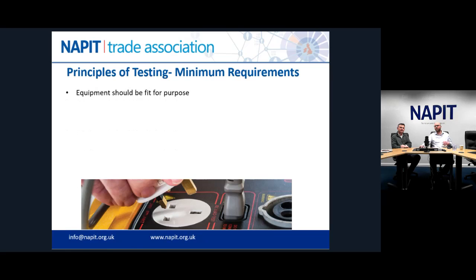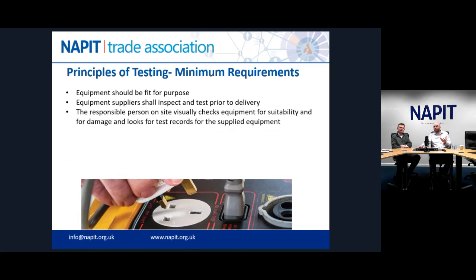So we've talked about this pre-testing. So the equipment should be fit for purpose when it arrives on site. The equipment suppliers should have inspected it prior to delivery on site, therefore the person responsible on site needs to check it. Visual, it's going to be a visual check. You're not going to do all your continuity checks. You've assumed that's done. Should there be test records that come with it?